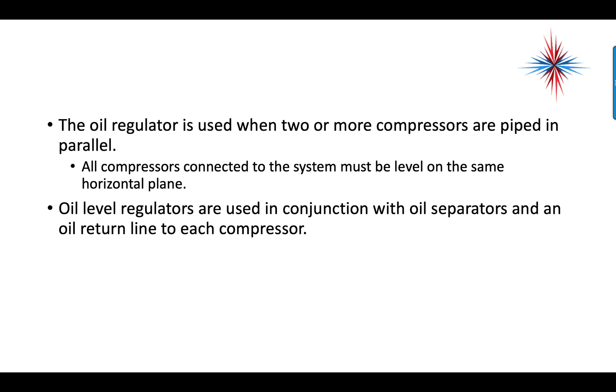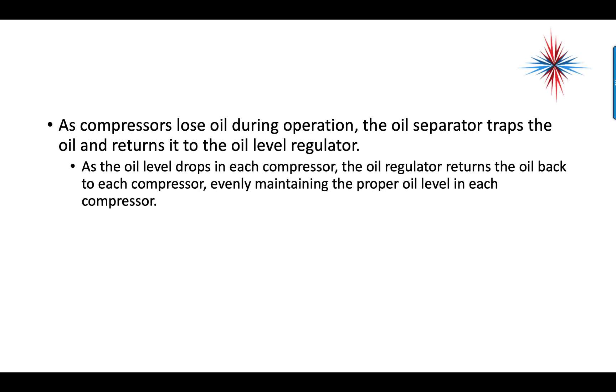The oil regulator is used when two or more compressors are piped in parallel. All compressors connected to the system must be on the same horizontal plane — they have to be level. Oil level regulators are used in conjunction with oil separators and an oil return line to each system. As compressors lose oil during operation, the oil separator traps the oil and returns it to the oil level regulator, which then returns oil back to each compressor evenly, maintaining the proper oil level in each compressor.